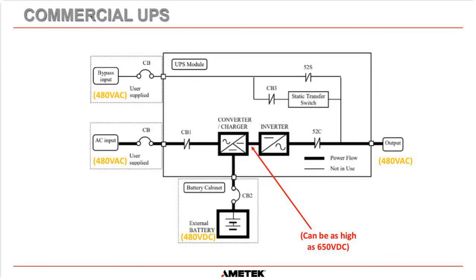And for a usual commercial UPS, you will have a 480 volt AC input. You will have a high DC battery usually on a commercial UPS. Usually it's a 480 volt battery, which is 240 cells lead acid. And the output is usually 480 volts, three-phase on a commercial UPS. And therefore, that means that the bypass has to be 480 volt three-phase as well, because the bypass must match the output of the UPS.